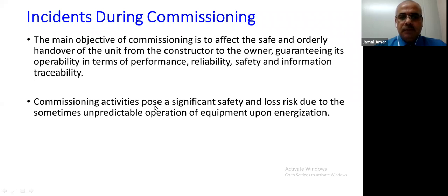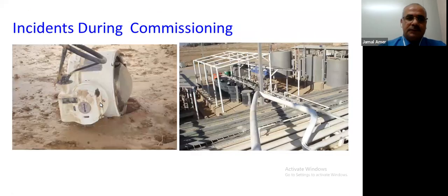So commissioning activity poses a significant safety and loss risk due to the sometimes unpredictable operation of equipment upon energization. As we see here, an incident during commissioning. What do you think of this one? Here we have a ball valve, and this ball valve was installed in this line. This incident happened during commissioning of a mega centrifugal pump, 1,100 barrels per day of water injection.